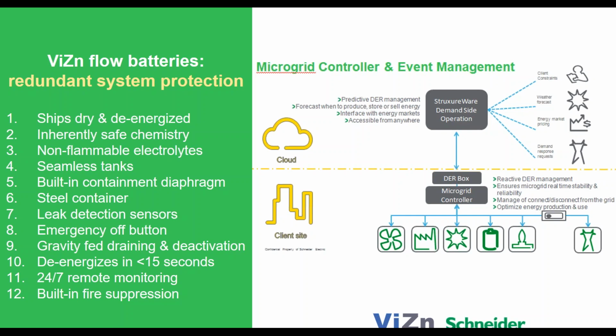One is, of course, the inverter, but more importantly for everybody on this call, there's the controls. The controls connect with the battery. You can see the icon in the center of the slide where it says microgrid controller, and right below it there's a battery-looking icon. It also connects to all the other distributed energy resources, the DER boxes. That's what a DER is, a distributed energy resource: wind turbines, solar, batteries, that kind of thing. That's how we set up the architecture and the controls so there are redundant systems for safety. That's the purpose.